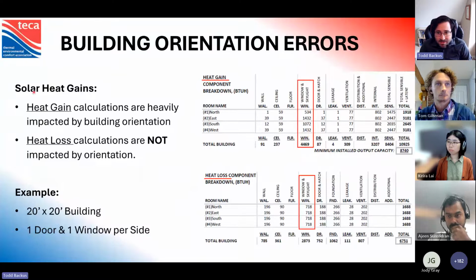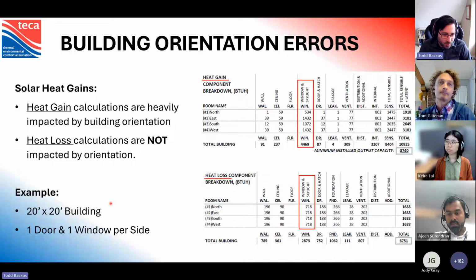So solar heat gains, when you're talking about heat gain, so cooling requirements, the orientation is important. Heat loss, it is not important for the orientation. So this is just an example of a 20-foot by 20-foot building with one door and one window per side. And you can see on the heat gain side, the windows change depending on the orientation, but the heat loss doesn't change.